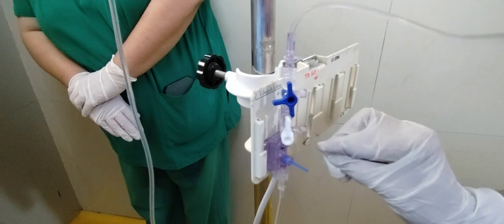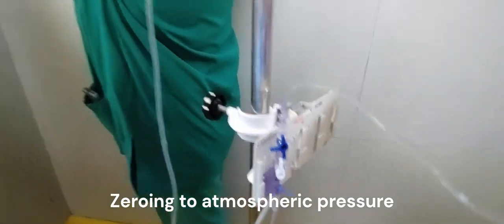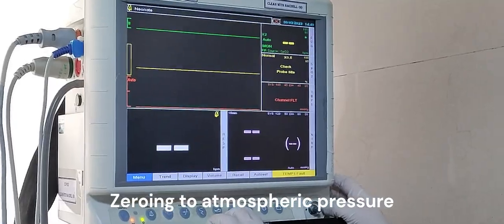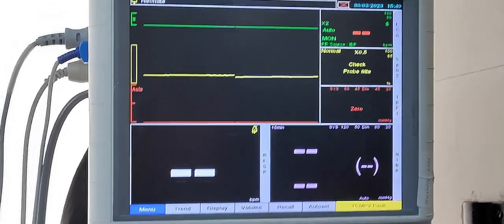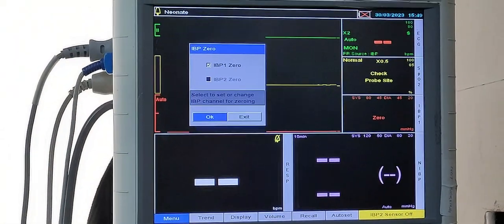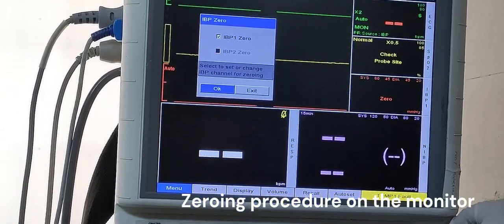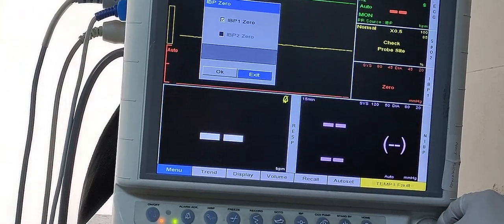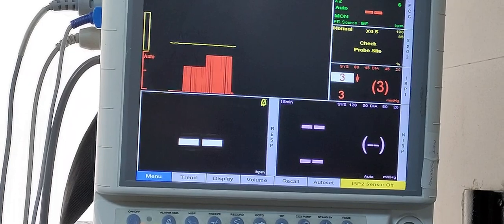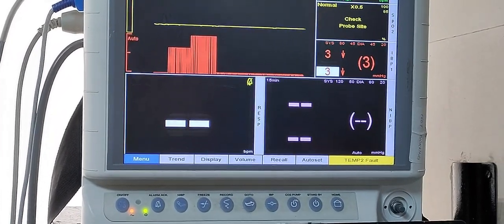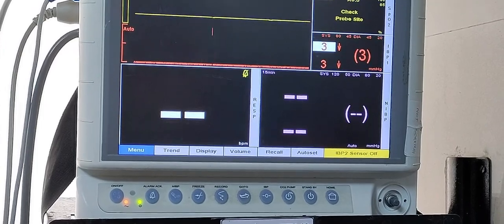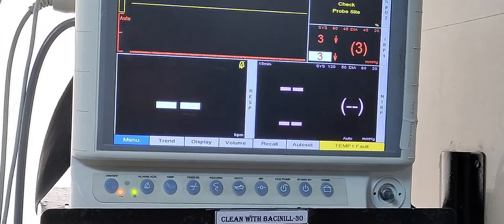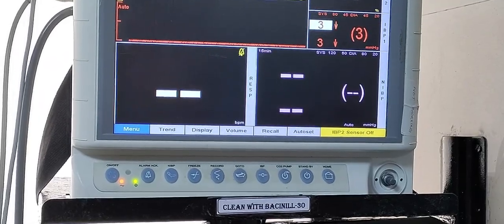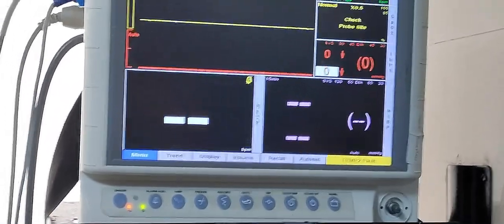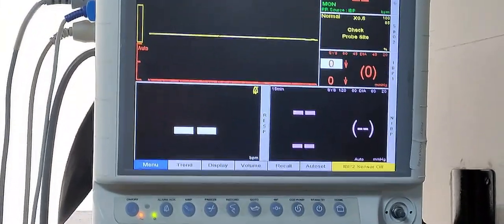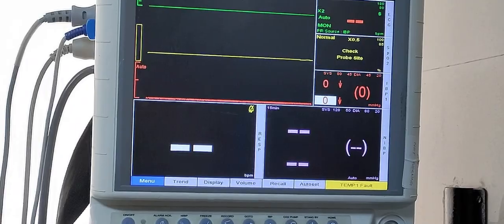Now we have to do the zeroing. Zeroing is done in the multi-parameter monitor. So once you connect, you need to press 0. You have to do the zeroing. Okay, so can you put OK? OK there. Yes. So it will take a while. Now zeroing has happened. That means now we have equilibrated to the atmospheric pressure.